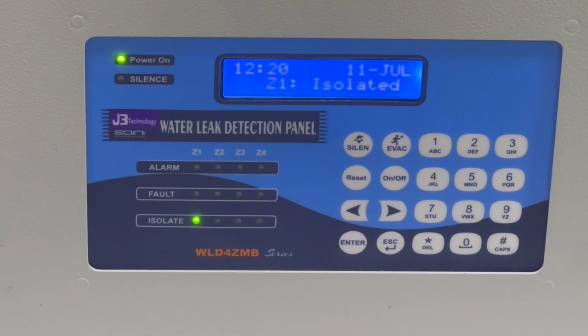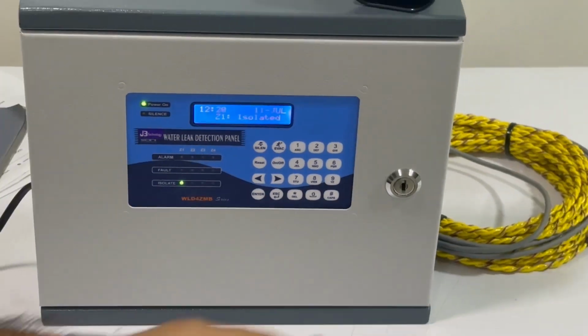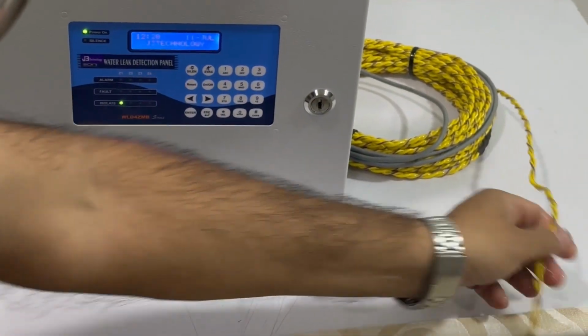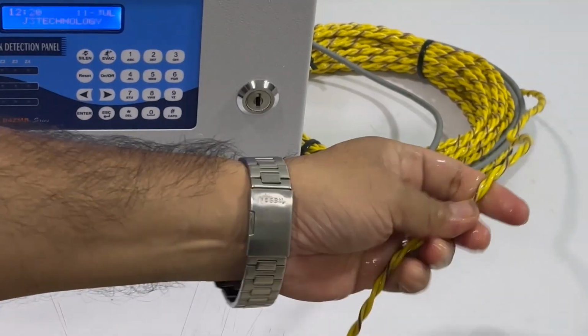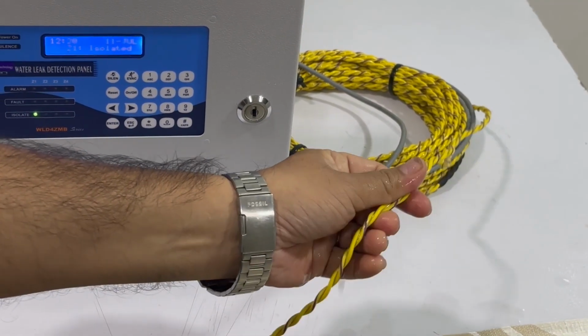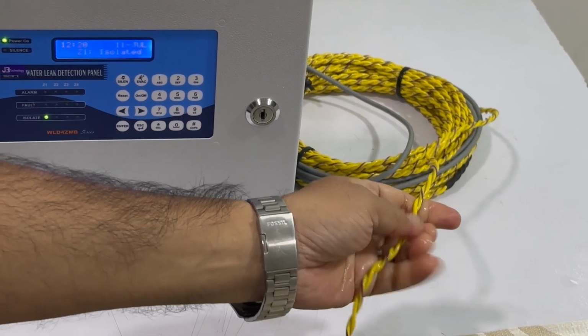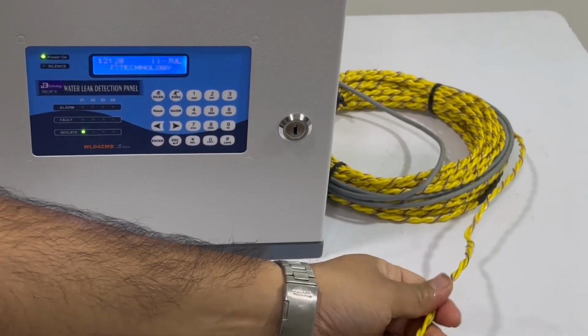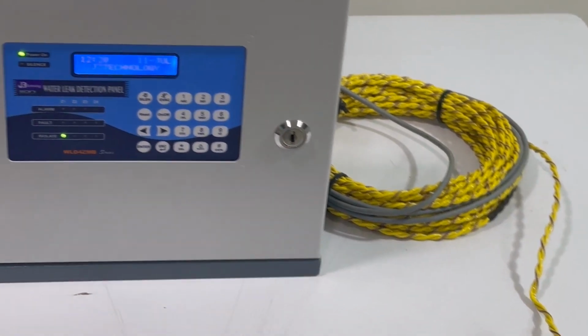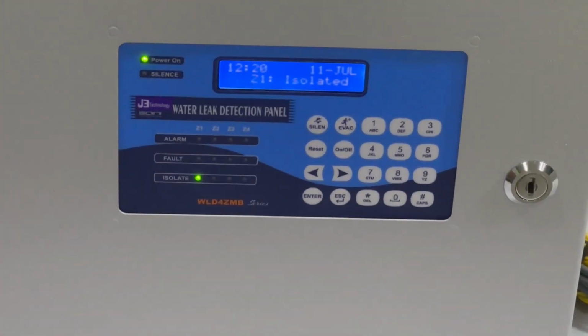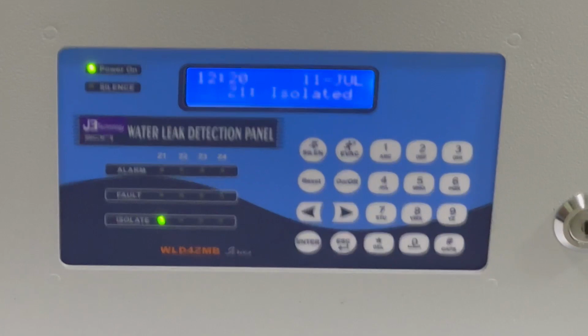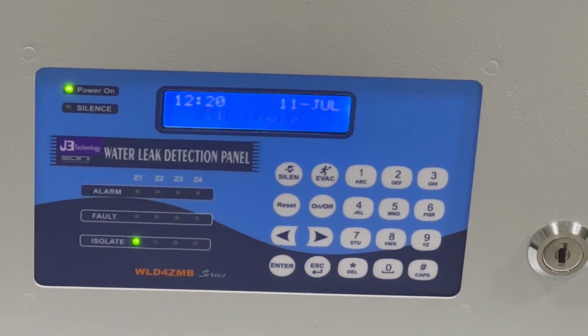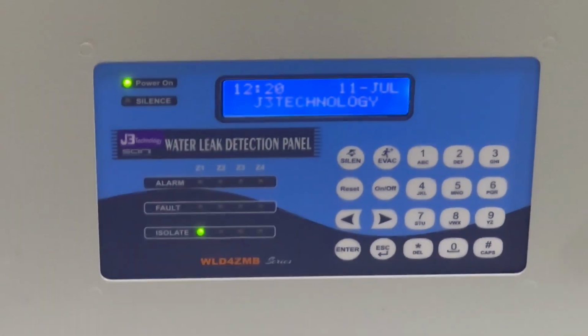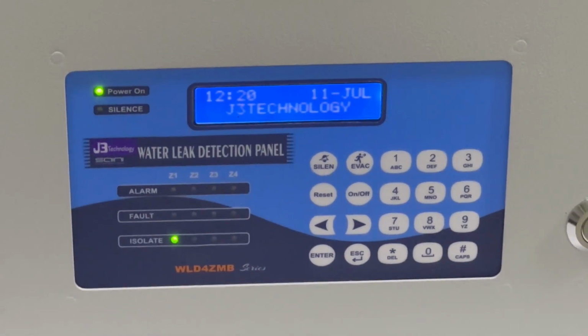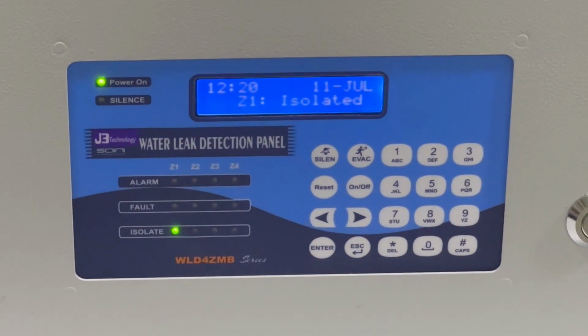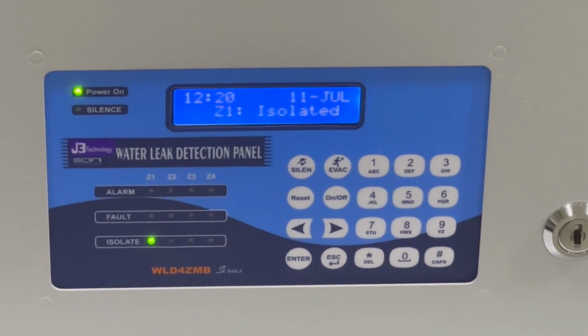I can show you that zone 1 is now isolated. By touching water or anything, it will not generate any alarm. See, it is not generating any alarm because that zone is isolated. No alarm will be generated. In that room some cleaning or some work is going on, so to avoid false alarms the isolate feature is kept on. So there will be no false alarm or disturbance to any other people.